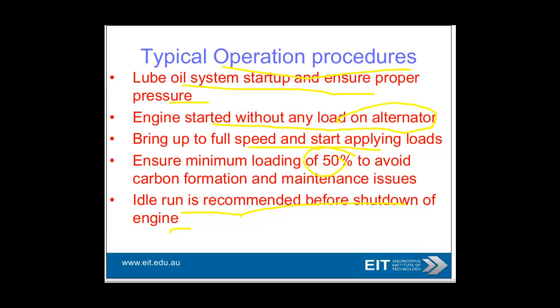We had one embarrassing situation where I was a consultant to a job where the software hadn't been set up correctly. I didn't write the software, I hasten to add. I wanted to test it beforehand, and of course the emergency generator diesel system, a Caterpillar, was put straight onto the grid. Needless to say, you hear the sound of brrr and then crash, stop. So obviously you need to start without any load on the alternator.